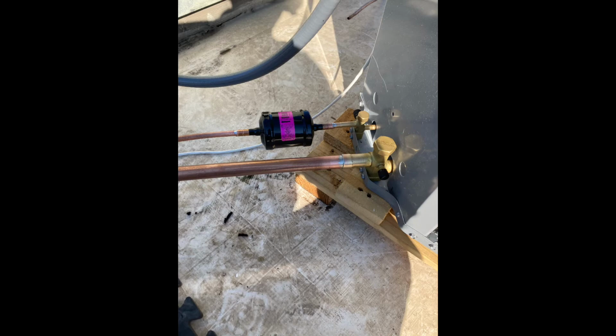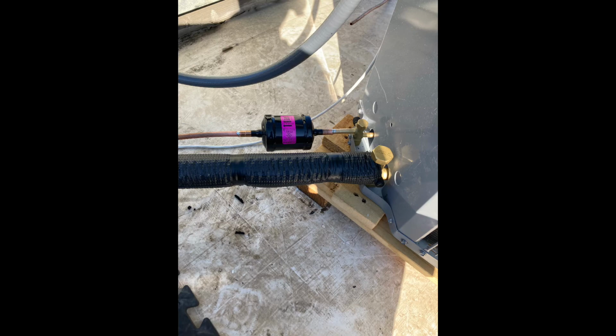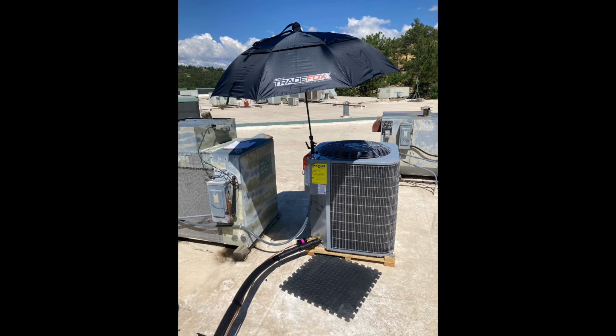So Stay Bright 8 is a quick and easy way to make your connections with your copper line set. It doesn't have to get near as hot as if you were going to braze it. Woo! We'll add our insulation to the cold suction line. Your suction line is a cold line. Your discharge line would be the hotter or the warmer line, the smaller one. So now that we had the line set ran and connected downstairs and on the roof, we can go ahead and pressure test the new line set and A coil with some dry nitrogen.